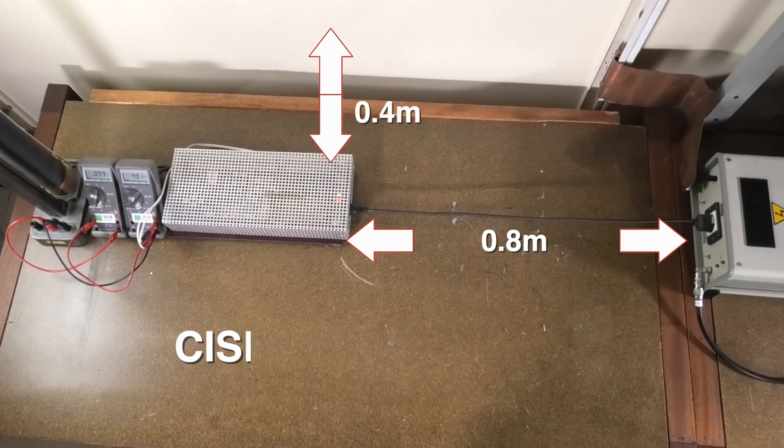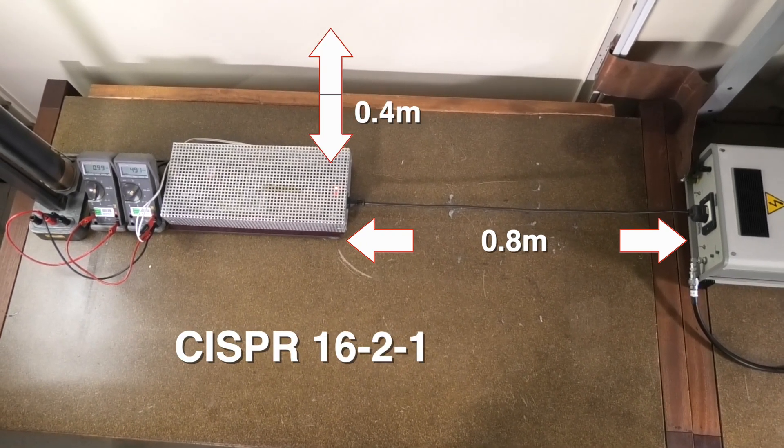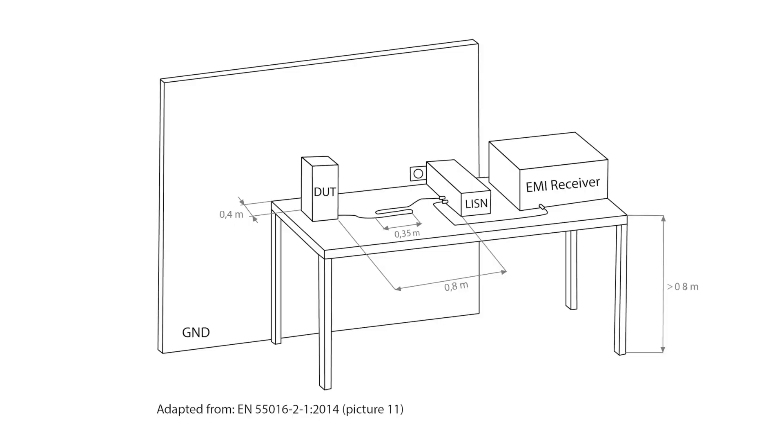By the way, this setup is not built in a random way, but attempts to meet the CISPR 16-2-1 standard as good as possible. This standard already specifies quite precisely how our measurement setup should look. I drew this picture myself, but it is quite similar to the one that you can find in the standard. From left to the right you can see again DUT, LISN and EMI receiver.